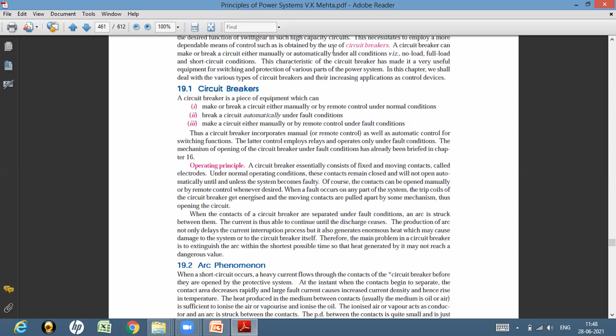The production of the arc not only delays the current interruption process, but it also generates enormous heat, which causes damage to the system or to the circuit breaker itself. I had also already explained this in my previous video. Whenever the circuit breaker operates under faulty condition, the moving contact and the fixed contact get separated. The moment they get separated, an arc is generally set up between these two contacts due to the very high current in the circuit breaker. So due to the arc struck between these two contacts, a lot of heat is produced, and this heat will damage the system as well as the circuit breaker.